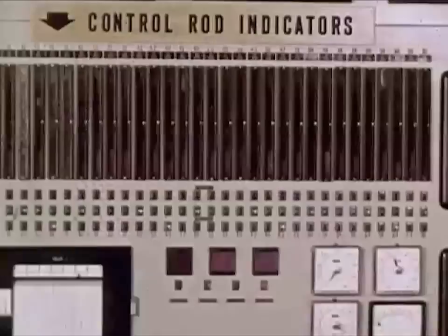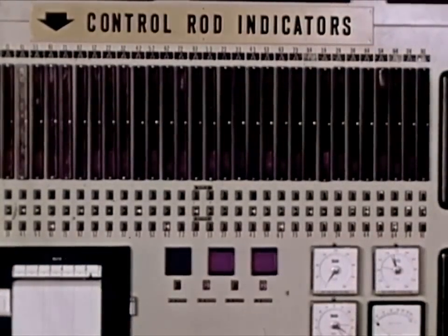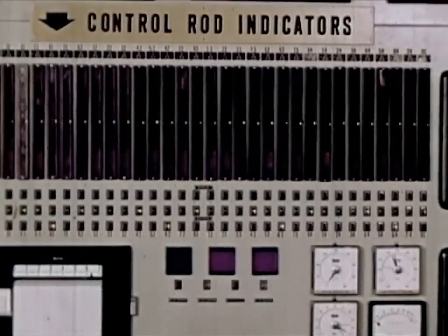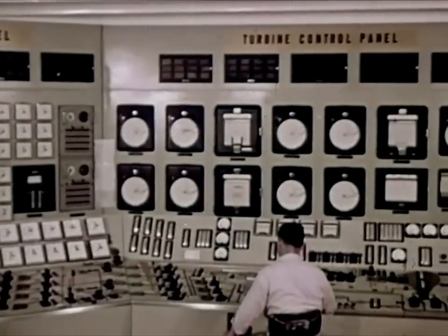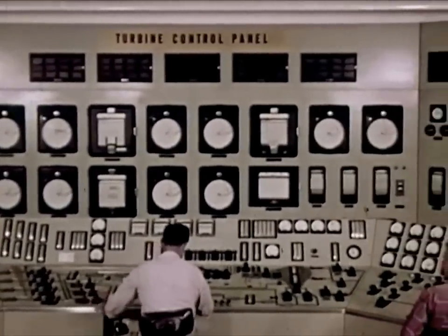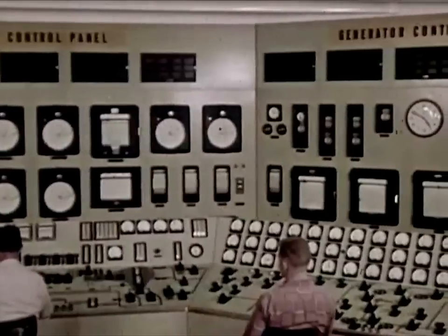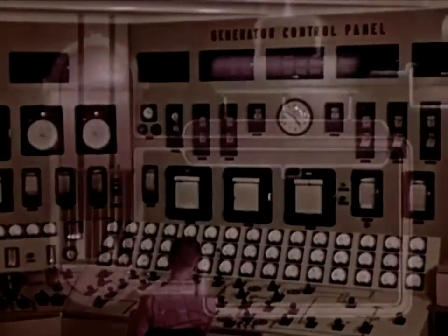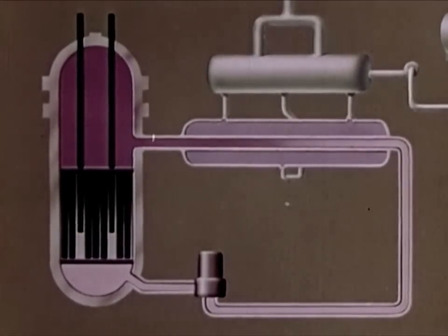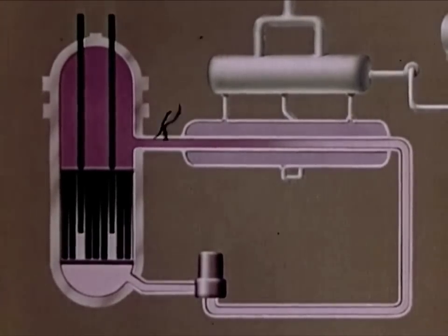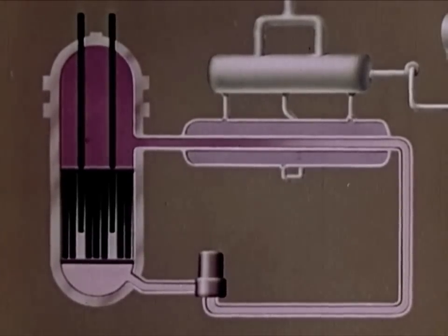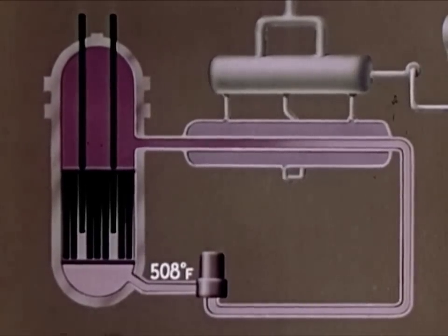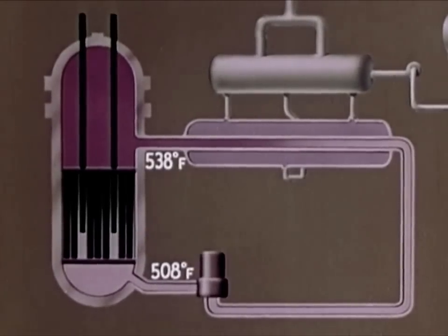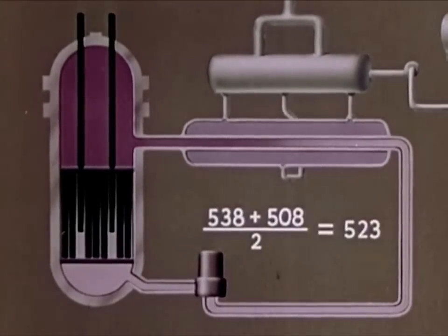To raise the power level, the control rods are withdrawn until the desired power is attained. Then they are moved back to the operating position. To lower the output, the opposite action is taken. No action is necessary to accomplish changes in electrical power demand imposed on this plant by the utility network. This is due to the large negative temperature coefficient of reactivity, which maintains a constant average water temperature in the primary circuit regardless of changes in steam demand. For example, if the inlet water temperature is 508 degrees Fahrenheit and the outlet temperature is 538 degrees, the average water temperature is 523 degrees.